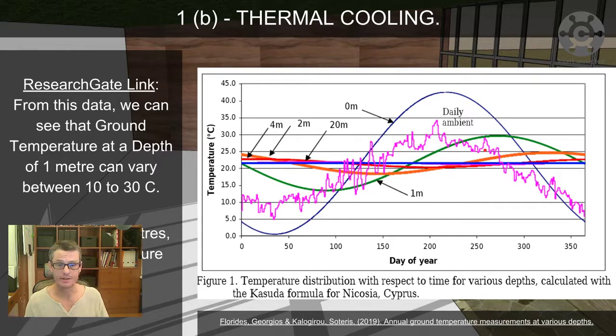So that's already a much more stable range of temperatures, 18 to 25, down to 2 meters. In terms of construction or excavation, that's probably not too difficult to get down to 2 meters. You start getting down to 4 meters, you're definitely going to need some much more heavy duty excavating equipment, shutters. You don't want to be in it if it collapses. So trenches for that kind of depth are much more difficult to construct. But 2 meters, it's probably doable without adding too much expense to that part of the project. And you get a really good 7 degree, basically, variation in temperature.